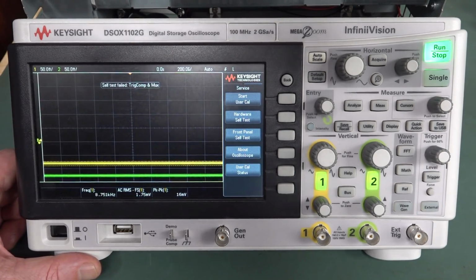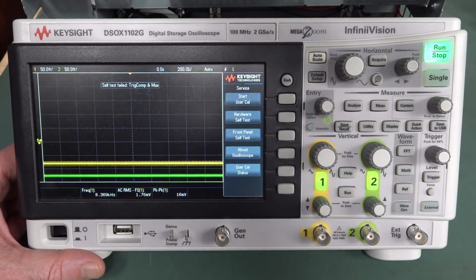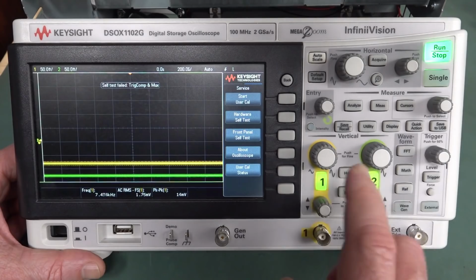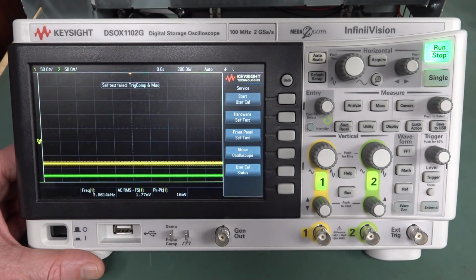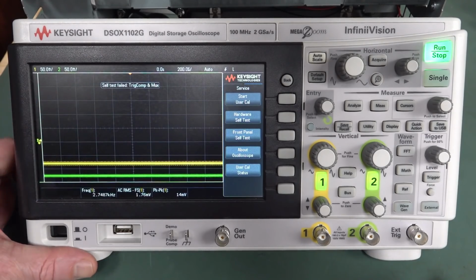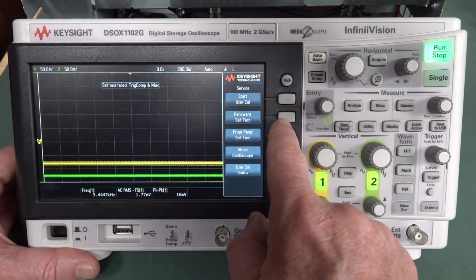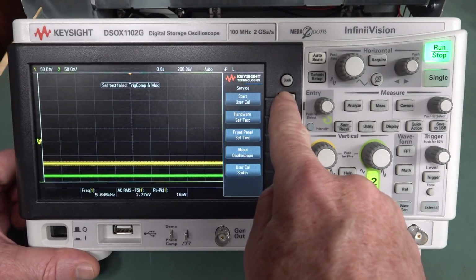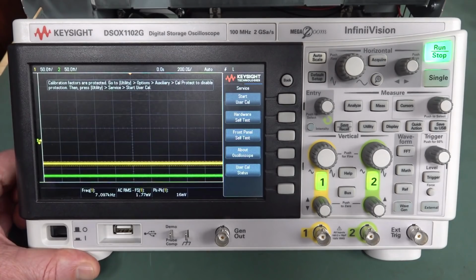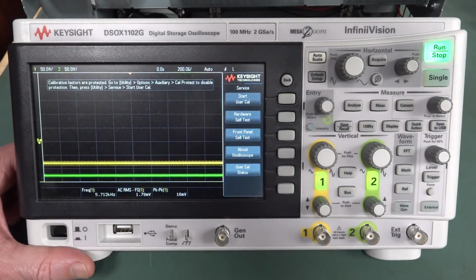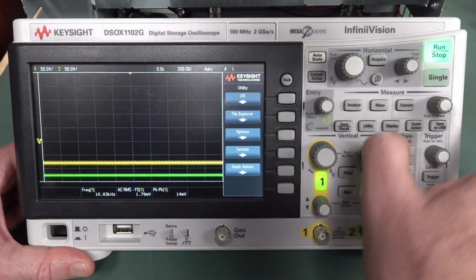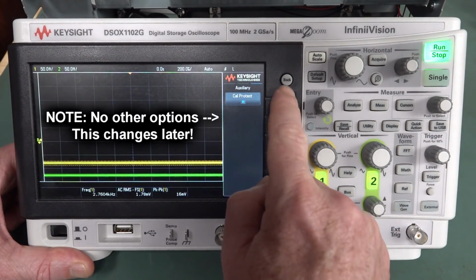Yeah, what's going on? It is the MegaZoom IV ASIC, so does it mux between the channels? I can't remember. Anyway, I don't know what mux they're talking about there, but it's interesting that those self-tests failed and not DC. Anyway, let's run a start user cal, shall we? So we'll give that a whirl. Calibration factors are protected. Go to utilities options. Oh god, we've got a cal protect disable. See, I would never have disabled the protection on this thing. So anyway, we're going to go disable that. Utility, options, auxiliary, cal protect, disable that, back.